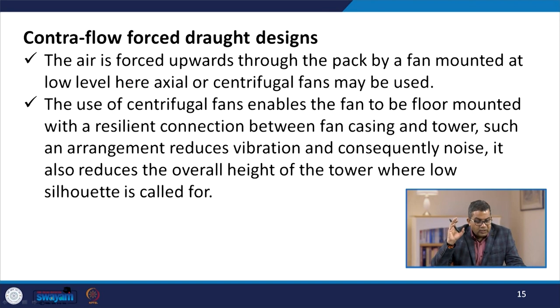Now, let us talk about the contra-flow forced draught design. The air is forced upward through the pack by a fan mounted at a low level, axial or centrifugal fans. Sometimes centrifugal fans may also be used. The use of centrifugal fans enables the fan to be floor mounted with a resilient connection between the fan casing and the tower. Such an arrangement reduces the vibration, because when all these axial fans are operated at a very high speed, there may be a chance of creating excessive vibration. This type of arrangement reduces the vibration and consequently noise.